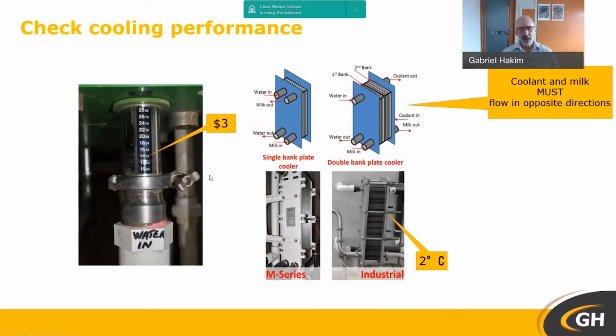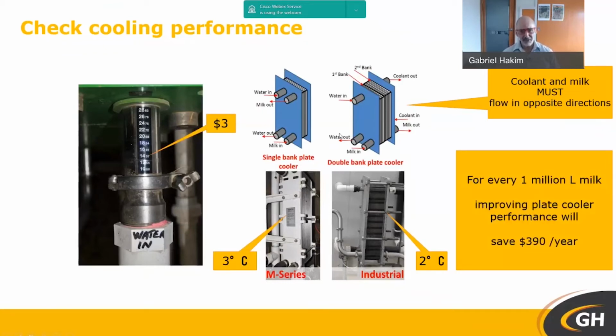So if water's going in at 18 degrees, milk should be coming out at 20 degrees all the time. For those who've farmed with the older style, plate coolers usually a lot smaller, it's a 3-degree difference. The thing about plate coolers is it's the cheapest way of cooling milk, because you're getting water from a bore or from a stream, and that bore water is usually around 16 to 18 degrees, so that means you can get milk into about 20 degrees.